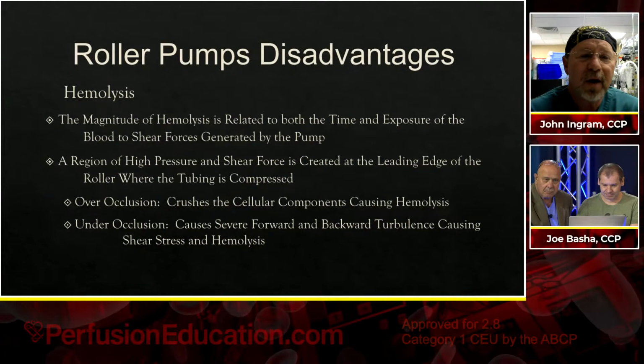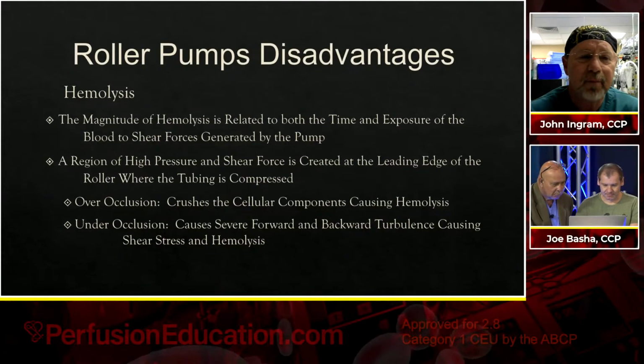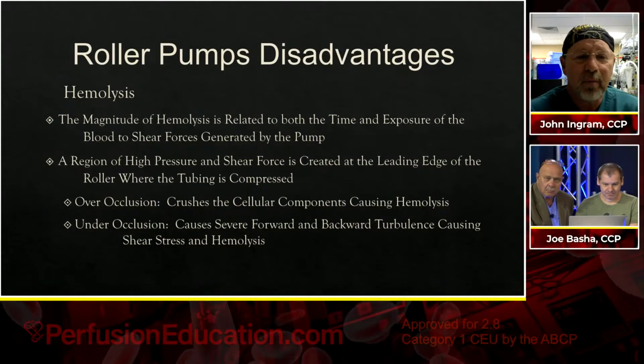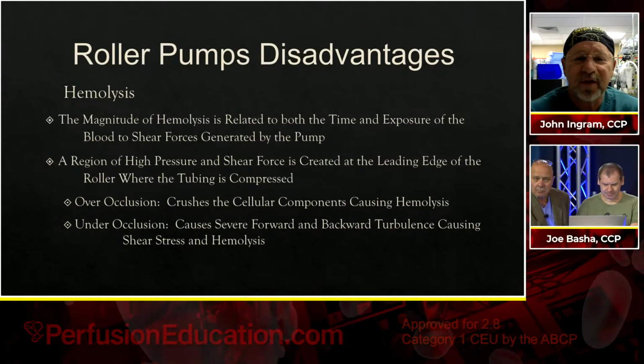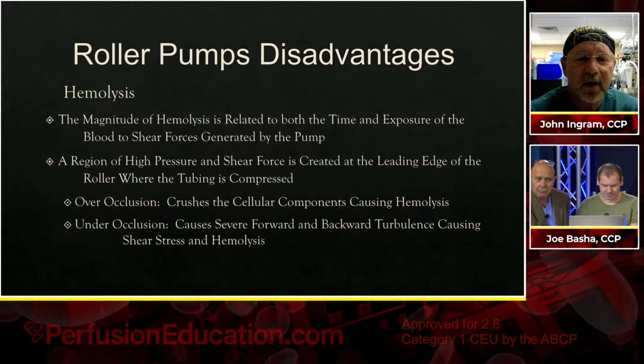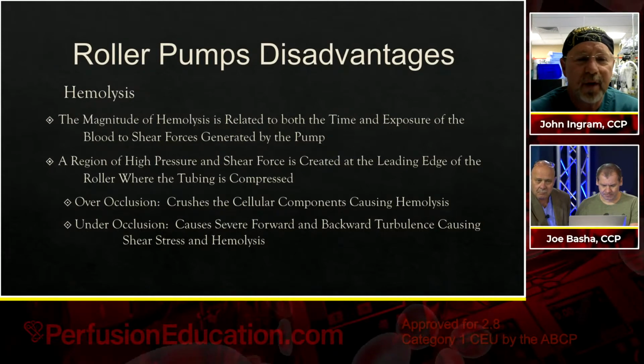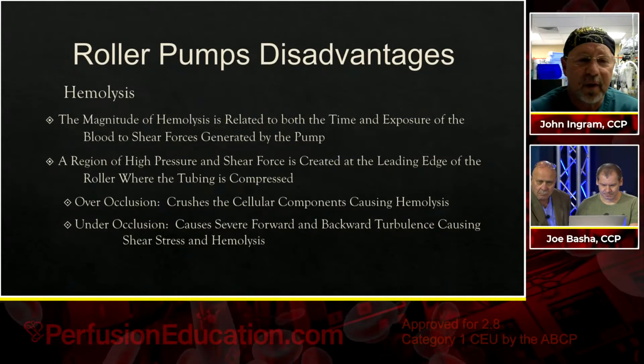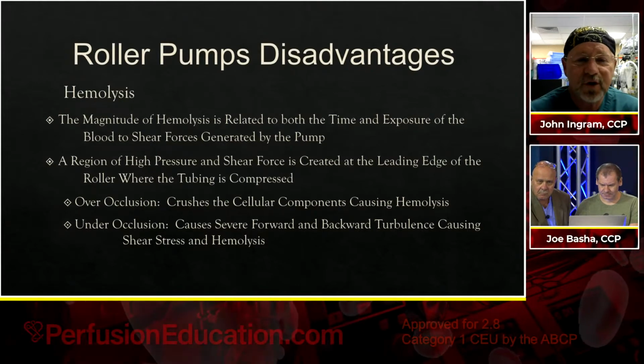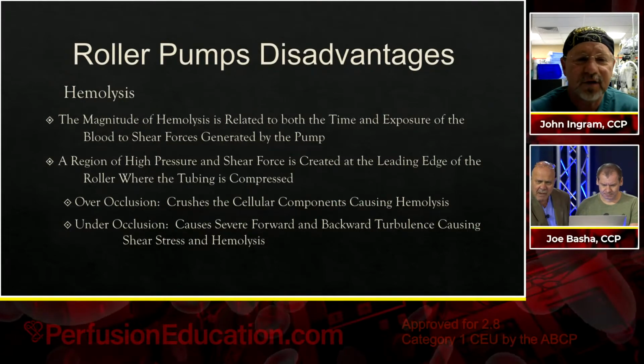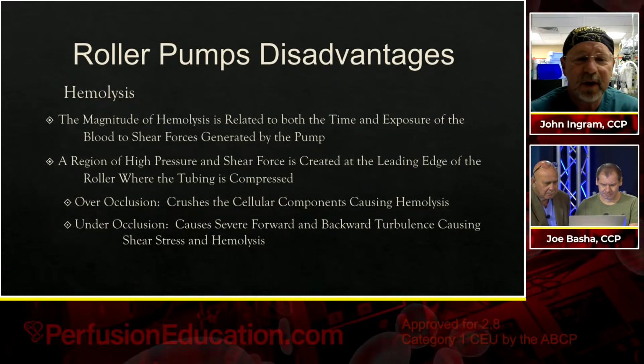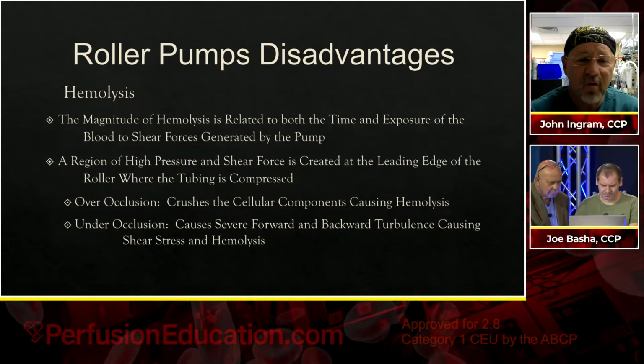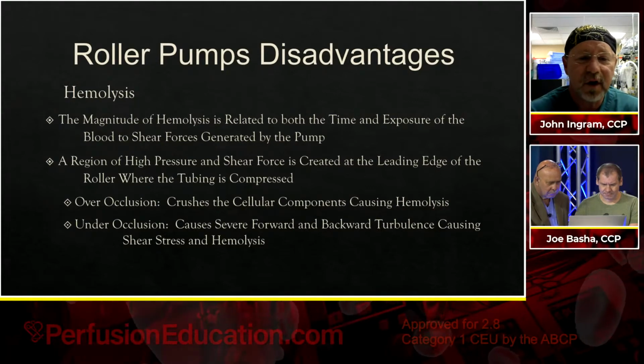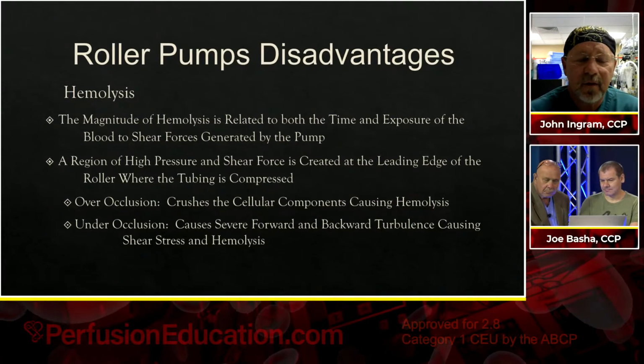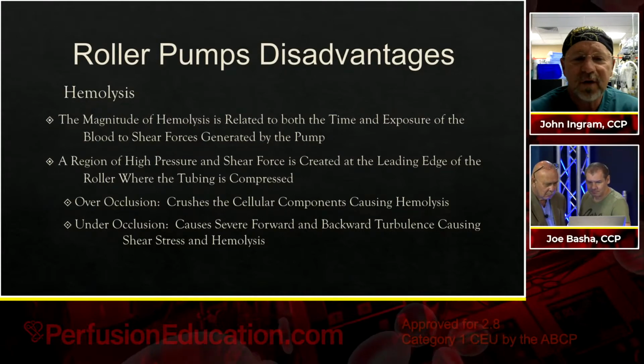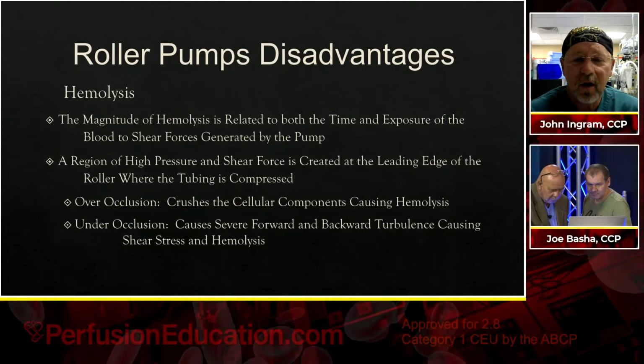Yep. So another disadvantage would be that it can be implicated in hemolysis. Well, the magnitude of the hemolysis is related to both the time and exposure of the blood to the shear forces generated by the pump. That's actually true of any kind of pump. There's a region of high pressure and shear forces created at the leading edge of the roller where the tubing is being compressed. Now, you can have an over-occlusion, you can have an under-occlusion. If you have an over-occlusion, the roller will crush the cellular components inside the tubing, causing hemolysis.